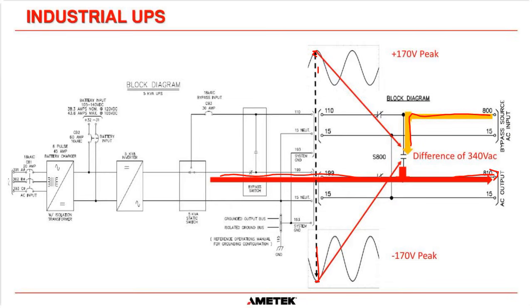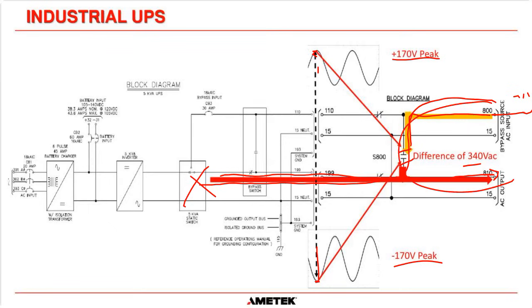Now, if you use calculation, the peak of the waveform is 170 volts. So up here, you've got plus 170 volts. Down here, you've got minus 170 volts. So across this contact here that you are about to close when you go to bypass to load, you are going to have a difference of 340 volts, okay? And what's going to happen usually is, because the bypass is a more robust source, it's going to feed into that difference, and it will try and feed back into the inverter IGBTs. So either the inverter IGBTs will blow, or the breaker that feeds the bypass source at the MCC, sorry, is going to trip. And if you just went to bypass, you're going to drop the load.